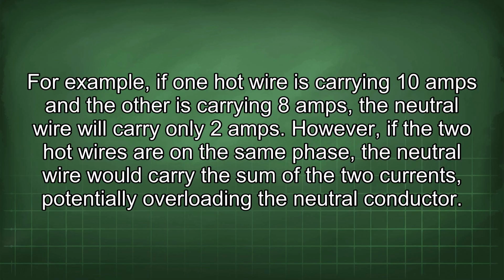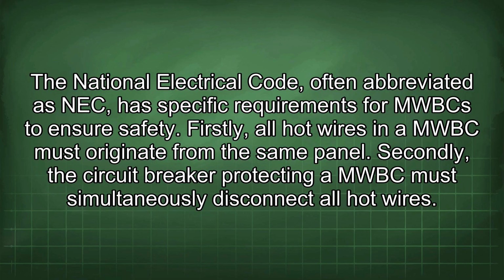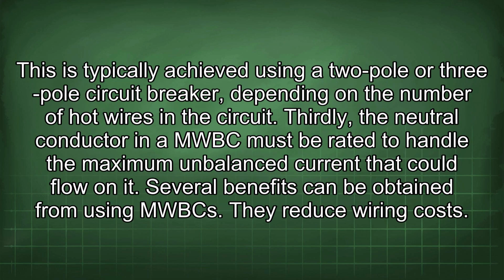However, if the two hot wires are on the same phase, the neutral wire would carry the sum of the two currents, potentially overloading the neutral conductor. The National Electrical Code, often abbreviated as NEC, has specific requirements for MWBCs to ensure safety. Firstly, all hot wires in a MWBC must originate from the same panel. Secondly, the circuit breaker protecting a MWBC must simultaneously disconnect all hot wires. This is typically achieved using a 2-pole or 3-pole circuit breaker, depending on the number of hot wires in the circuit.